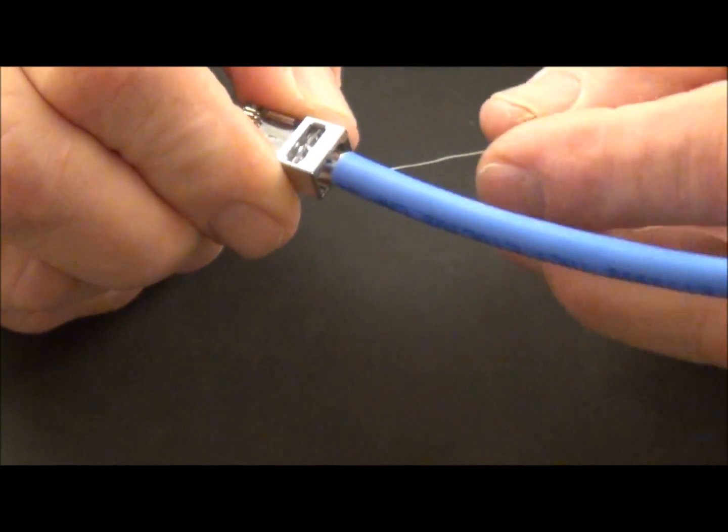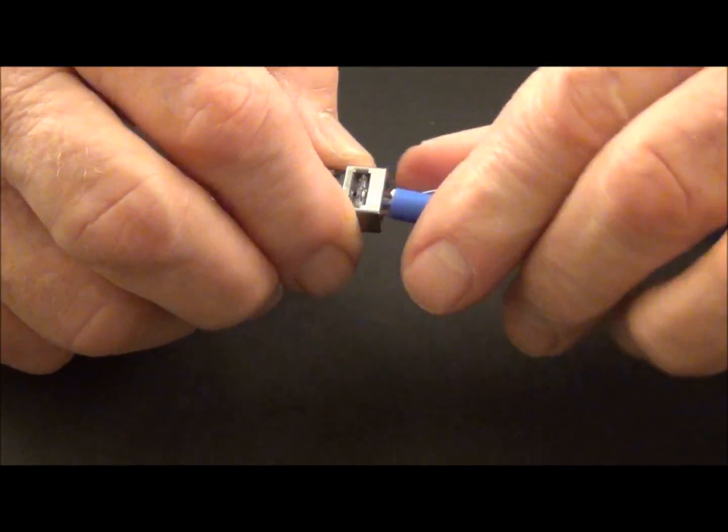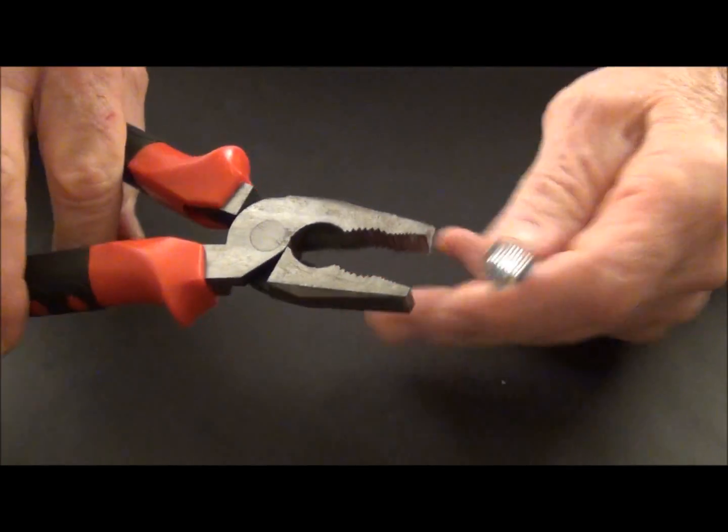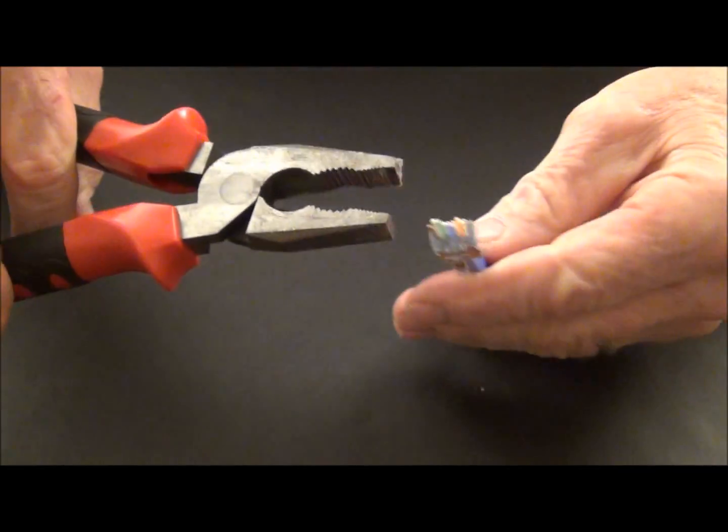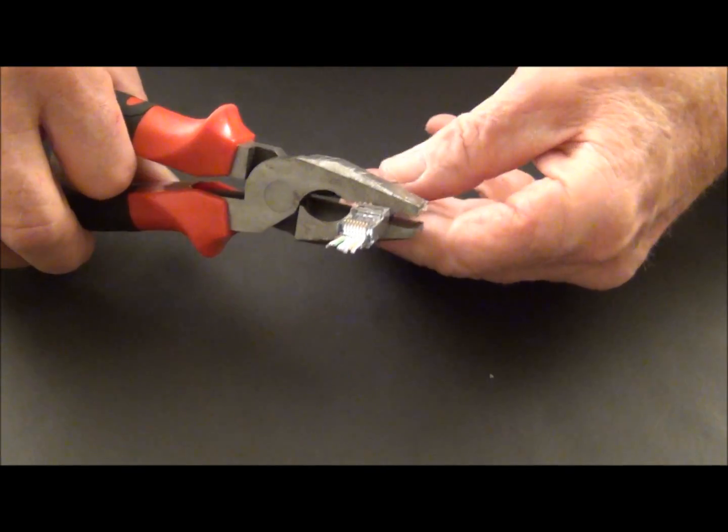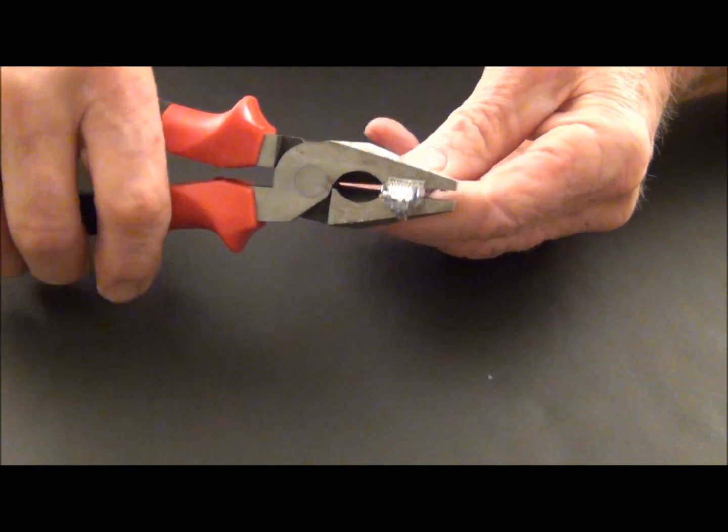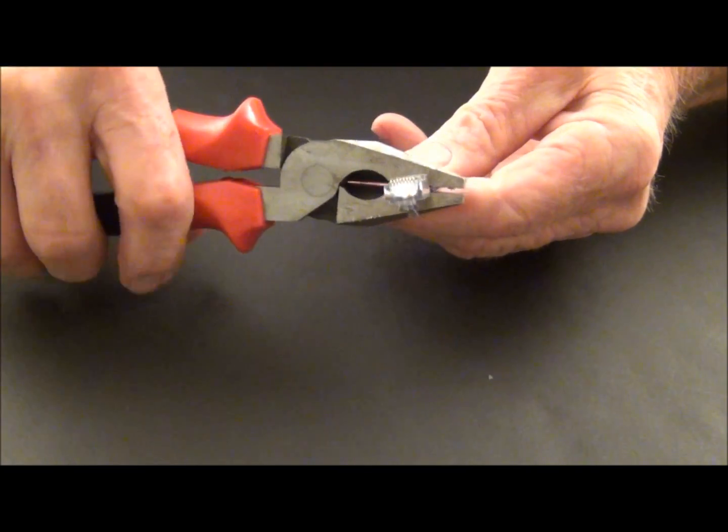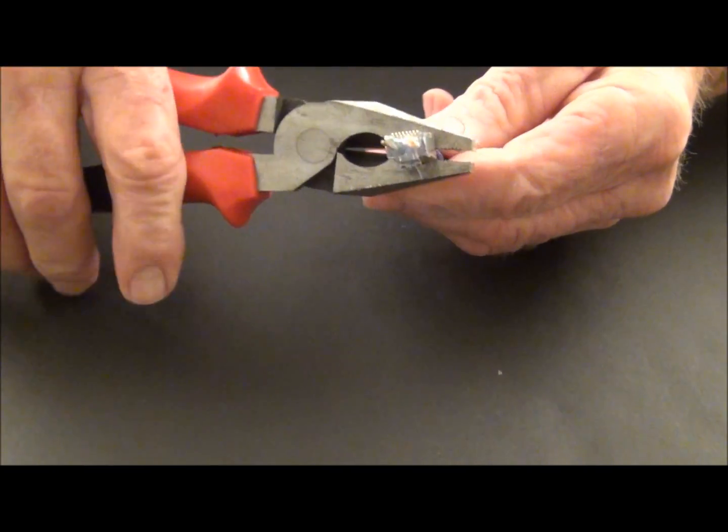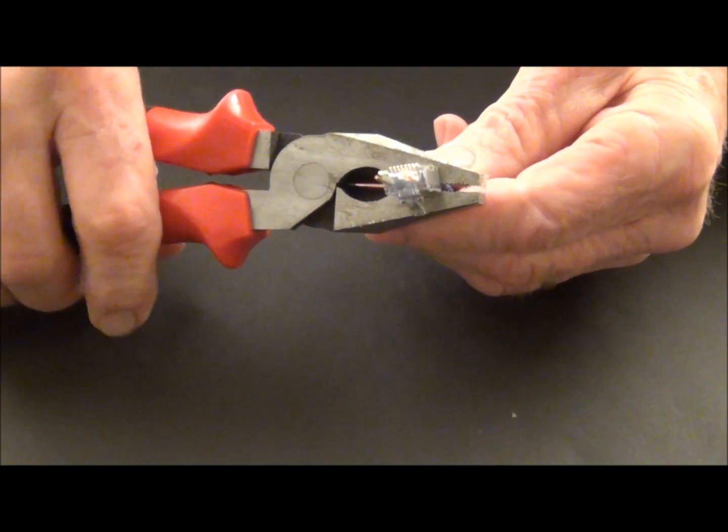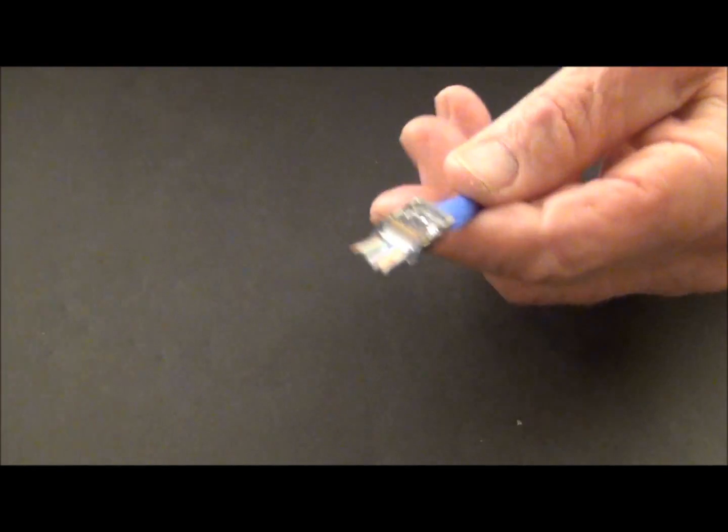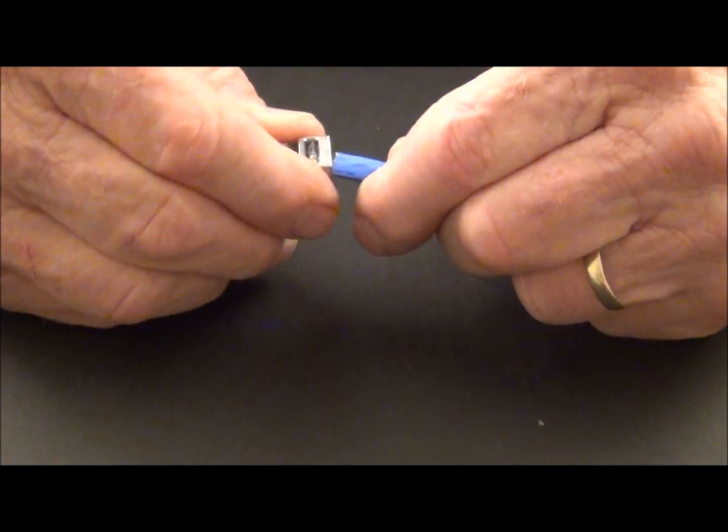So a little trick to help us here is to use the oval or grip part of my pliers. And I'm going to use these out of my toolbox here. And I'm going to use this part of the tool. And not real hard, but I'm going to shape it to ovalize it so it enters the back end a lot easier. And go up into the cable. And that does not take away from certification.